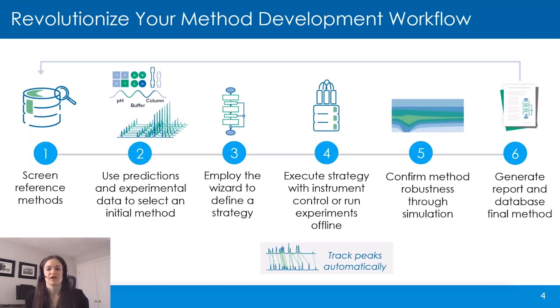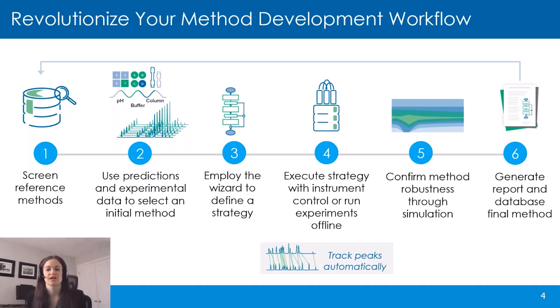Searching reference methods and using predictive tools can help you get a superior starting point and allow you to intellectually optimize your method. In the software, there are tools that can help you select the right column for your study, as well as tools to help with pH selection and buffer suggestion. One of the tools we have is AutoChrom, which has a wizard that can help define a strategy for optimizing several parameters like pH, gradient, and temperature, while setting success criteria like resolution, retention factor, and runtime before you even run a set of injections. Once your strategy has been defined, the system will suggest experiments and allow you to execute them.